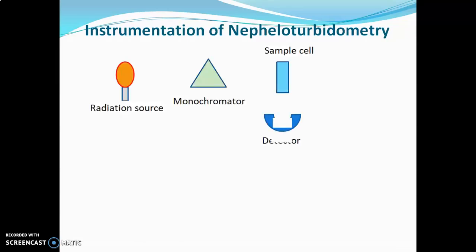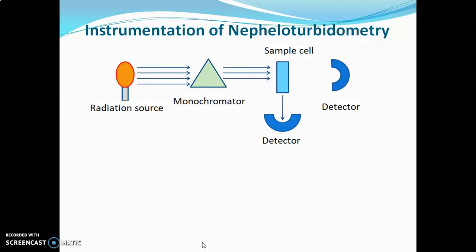Now, for the instrumentation of nephelo-turbidometry — if both techniques are combined, there will be a radiation source, monochromator, sample cell, a detector at 90 degrees to the radiation source, and one more detector at 180 degrees to the radiation source. If two techniques are combined — nephelo and turbidometry — two detectors are placed or one concave detector is placed. Radiation source emits radiations, which pass through the monochromator, then through the sample, where scattering or transmission of light occurs, and these are recorded by the detector.